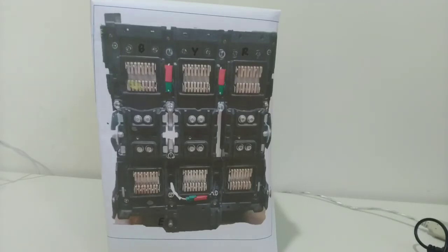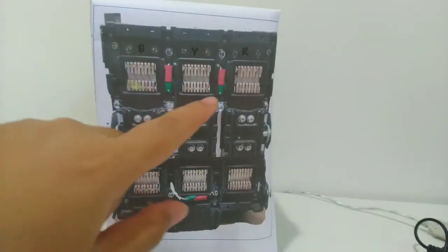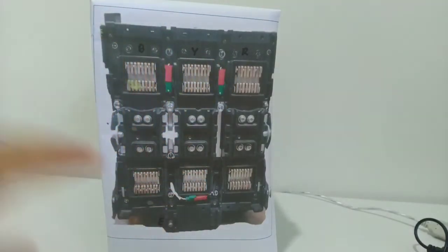Now we need to do this test in two situations, where the ACB is in the closed or open position. In closed position of the ACB, we need to test phase to phase and phase to earth terminal. Here are the phases and this is the earth. I already labeled the red, yellow, blue phase and earth. First, we need to make sure to check whether the ACB is in on or off condition.